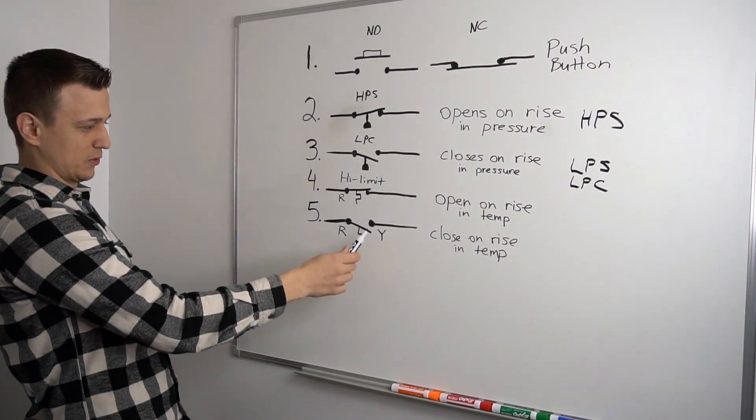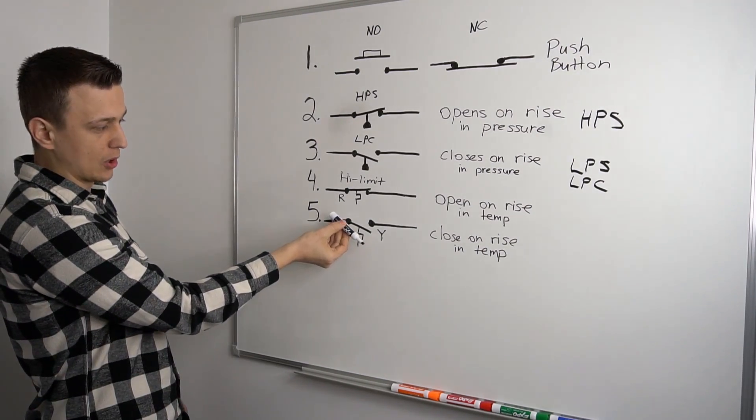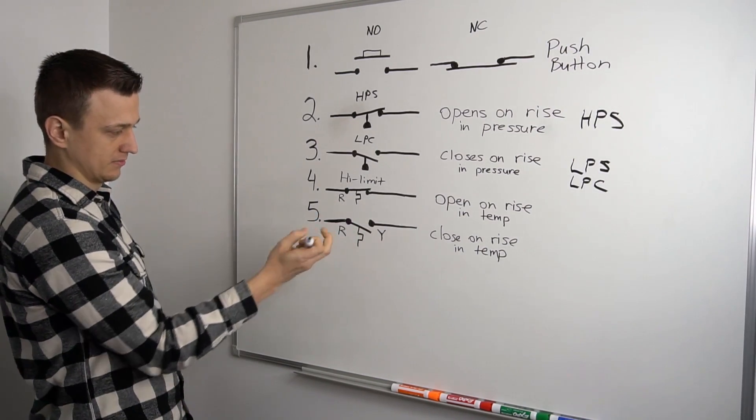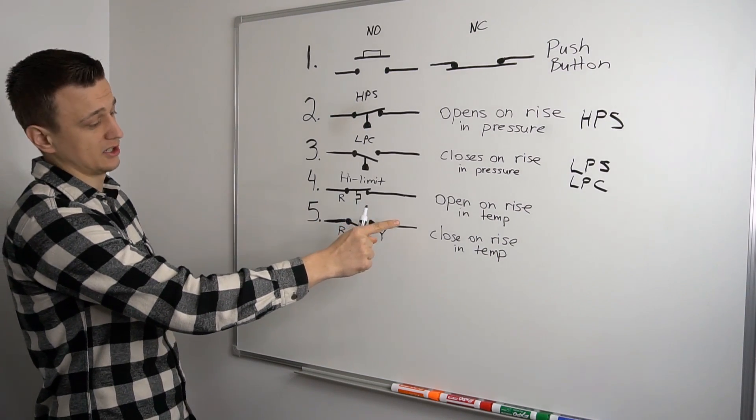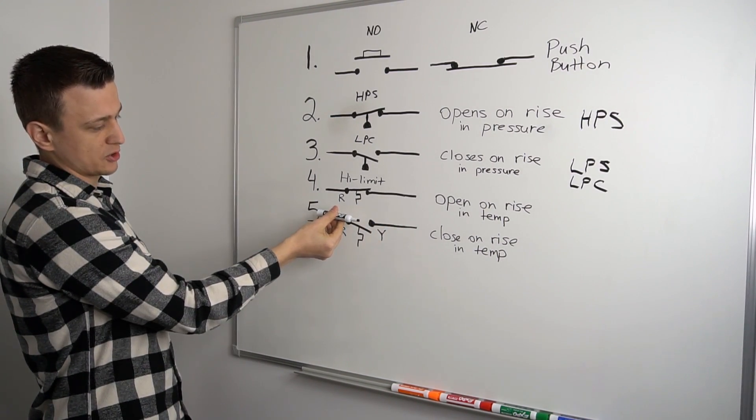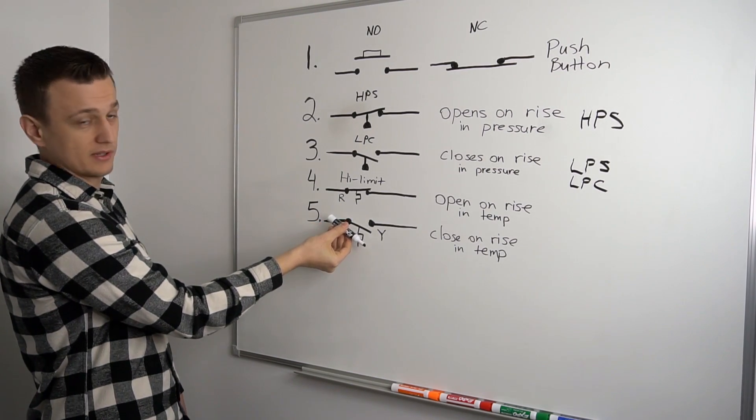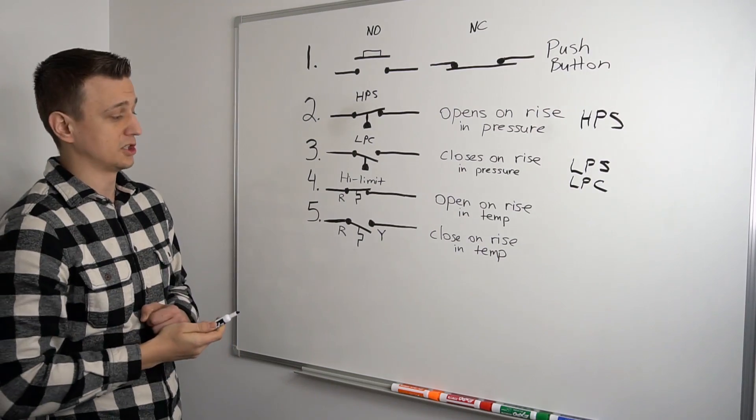So this switch, if it gets hotter in the house, this temperature switch starts to go up until it makes a connection. Boom. It sends power to the air conditioner through Y. And once it cools off enough, the temperature in the house or around the thermostat starts to drop again. So that switch opens back up, interrupts power, and turns the air conditioner off.